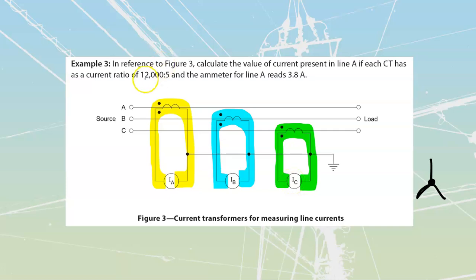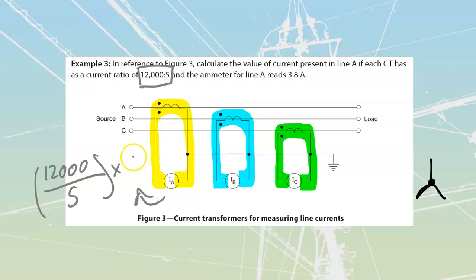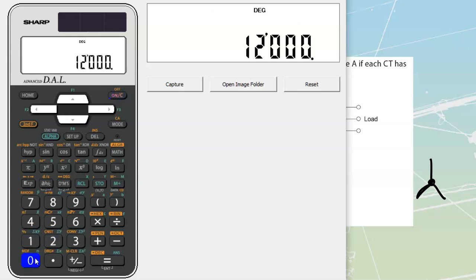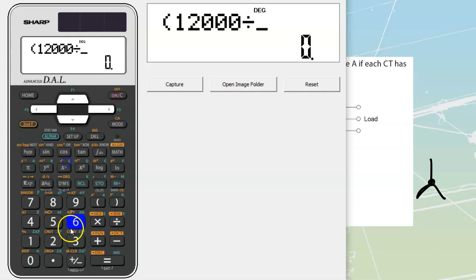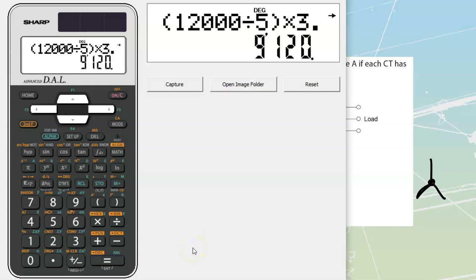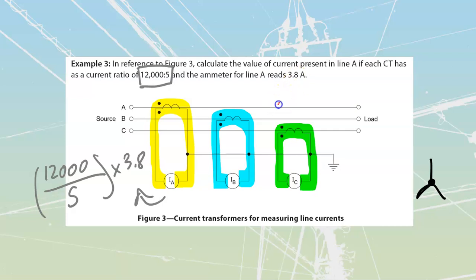It says each CT has a current ratio of 12,000 to 5, and the ammeter for line A is reading 3.8 amps. Well, if we know our ratio, 12,000 over 5 amps, we can take that ratio and multiply it by our actual reading over here, 3.8 amps. So let's do that. 12,000 divided by 5 multiplied by 3.8 gets me to a value of 9,120 amps. That's what I've got going out to my load.